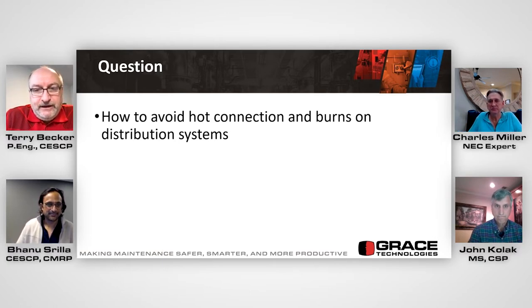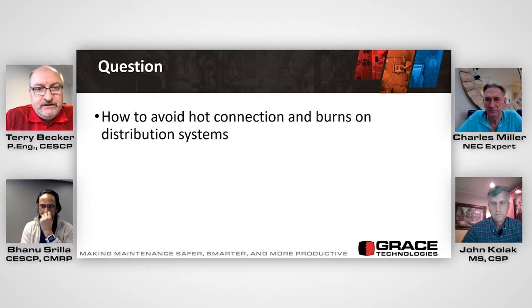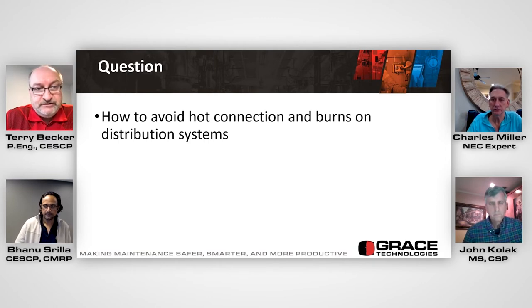Can I just add a comment? In Canada, we created the CSA Z463 Maintenance of Electrical Systems standard as a guideline in 2013, which became a standard in 2018. Something that's different in it than NFPA 70B is we're talking about maintenance for safety, exactly what John said. We need to prioritize maintenance on our electrical protective devices that we're relying on, for instance in energy calculations and/or clearing times if we're using the arc flash PPE category table method. So use maintenance for safety, use risk assessment as a tool for arc flash and shock hazards, but use it for maintenance as well. Risk assessment is a powerful tool to help make decisions.